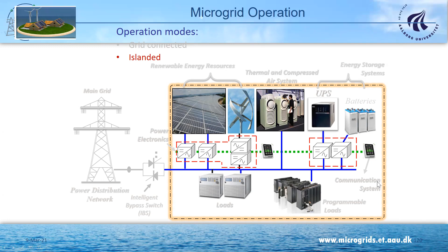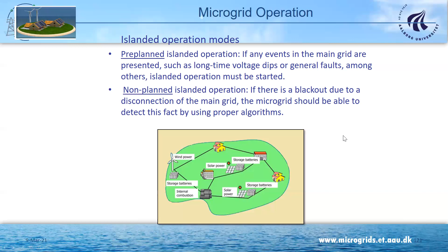However, sometimes we have blackouts, and this is what we call non-planned islanding operation. When there is a blackout, we need to detect that we are really disconnected from the grid. Otherwise, imagine a guy who's repairing some parts of the grid, and he disconnects upstream, thinking nobody's injecting power. Then we could kill this guy, or we could damage a lot of equipment. That's why it's very important to detect that we are in island very fast.